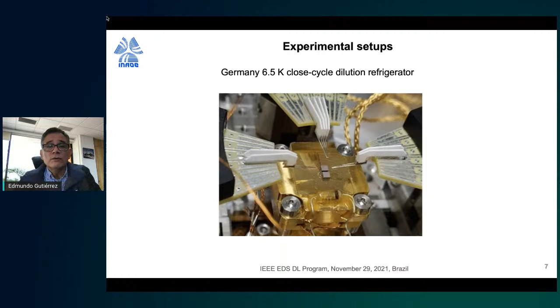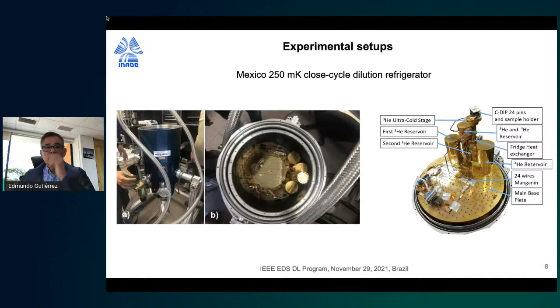Then we have the Mexico 250 millikelvin closed cycle dilution refrigerator. This is a big instrument, and there you may see the sample holder and some of the different temperature stages. We have the helium 3 liquid ultra cold stage, and the reservoirs for the liquid helium 3. Then on the top at the right side of the picture, we have the socket with the sample holder where we put the packaged devices. This is the general configuration of the experimental setup that we have in Mexico.